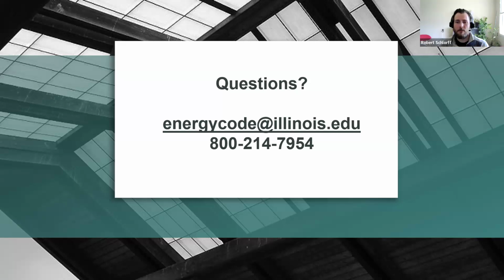And we do have some online modules that talk about that already and some other resources. So if you can't find what you're looking for, ask us a question and we can help you out. And then summarizing the requirement for manual overrides for controlled lighting and receptacles in open office areas. So anywhere that you have an occupancy sensor that can automatically turn the lights off on a time delay, you have to have an ability to manually override them off by the occupant in the space, in case they want the lights off before the sensor would trigger them off, or the sensor can't trigger them off because there's an occupant in that space.